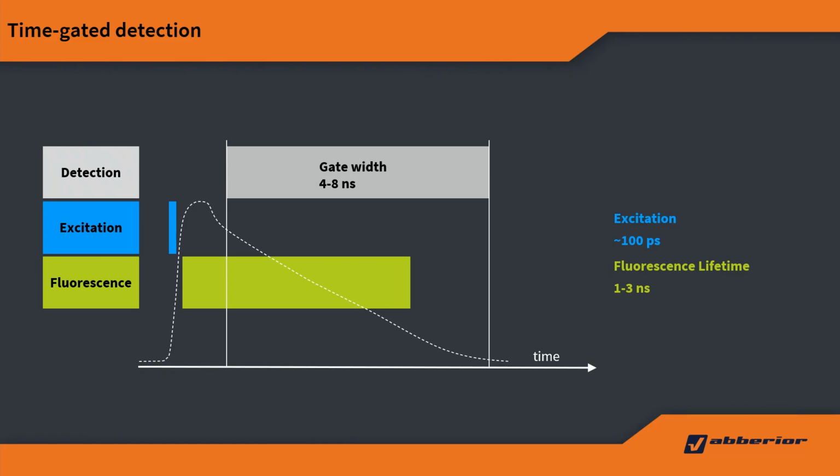Why do we have time-gated detection? Well, that's because we are using a completely pulsed system with also a pulsed STED laser. And that allows us really to wait until the STED pulse has done its job, meaning giving us super resolution, and then only detect photons coming after this job has been completed, meaning we're getting the sharpest image for the least irradiation of the sample.